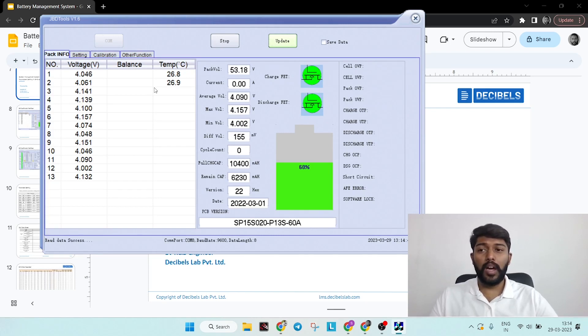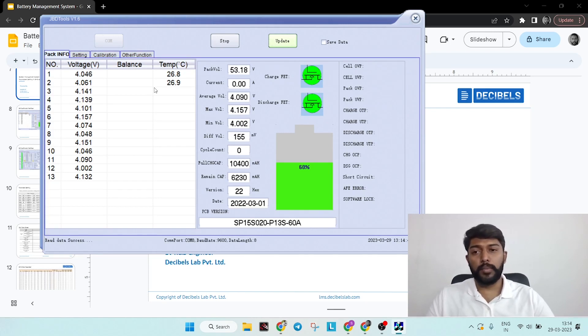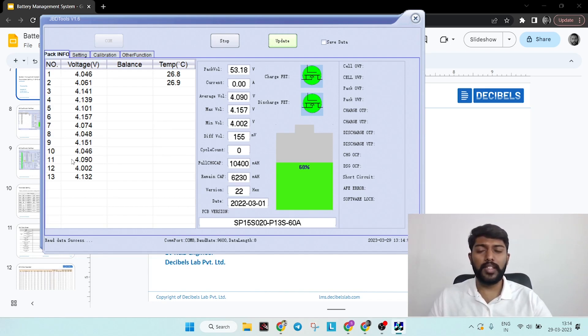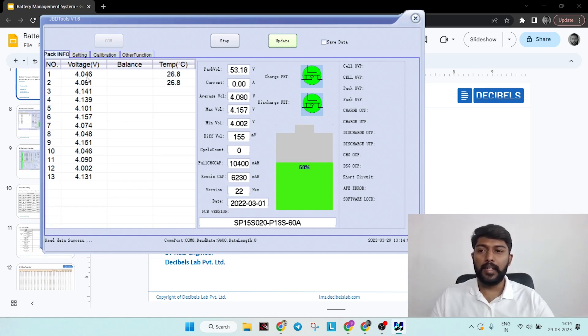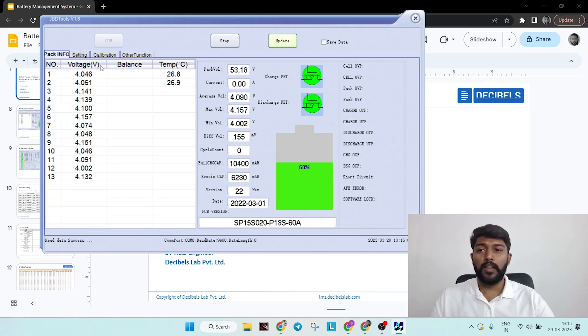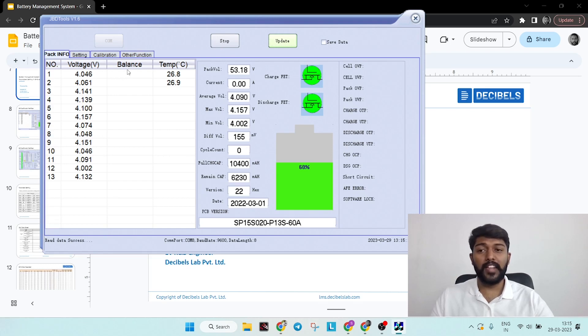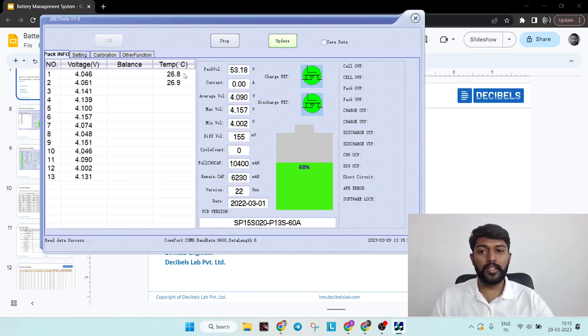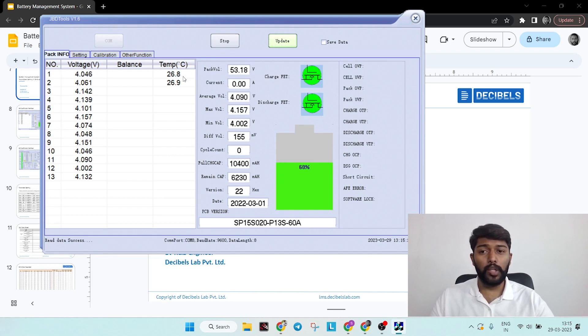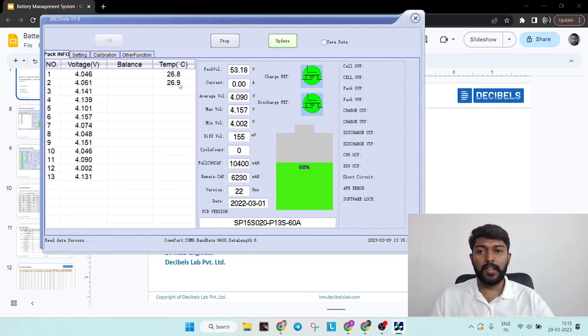First on the screen you see pack information, where you can see for all the series, voltage ratings will be indicated, starting from series 1 to 13. The voltage is slightly varying currently. Beside you have balance - anytime a self-balancing or series balancing takes place, there will be an indication of ON in this column. Then you have two temperature measurements with the battery pack - one is onboard, and another one is connected inside the battery pack.